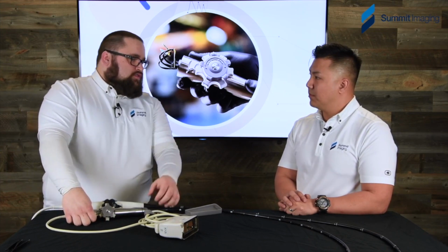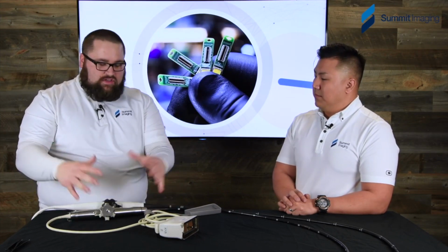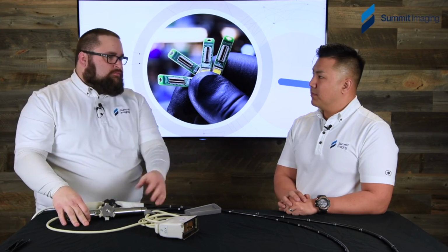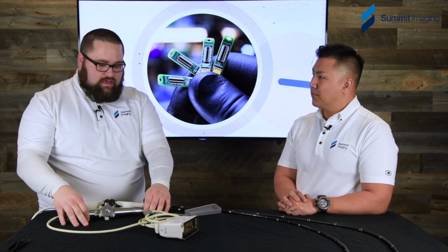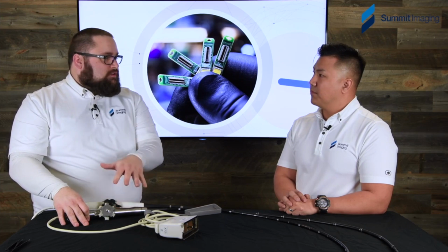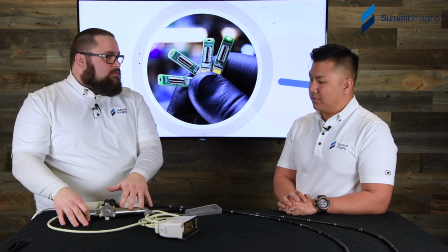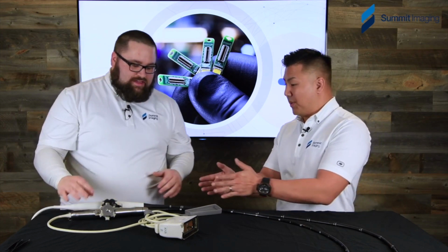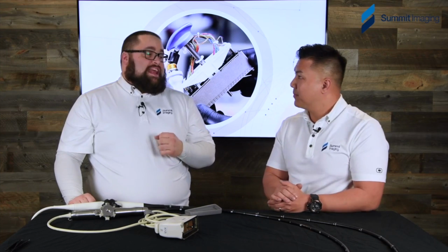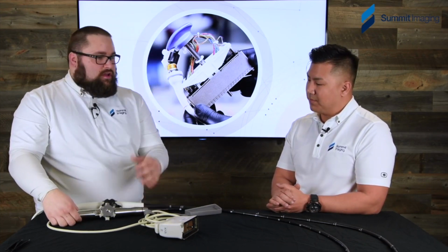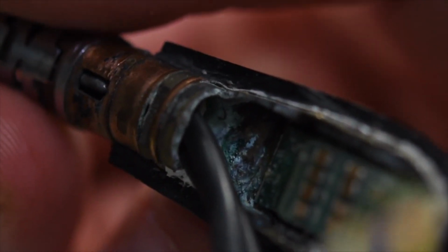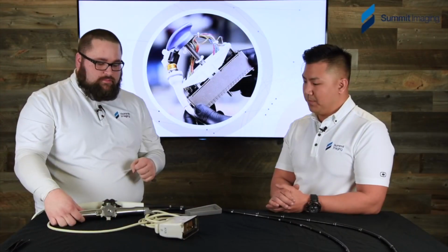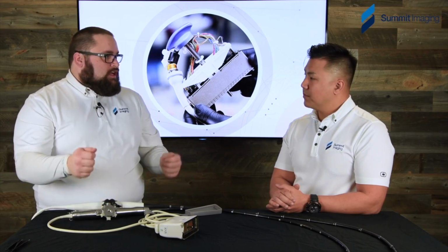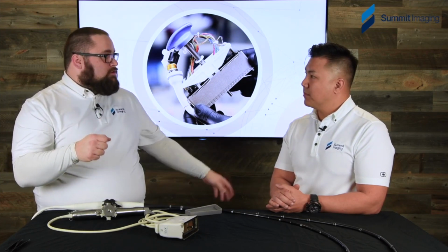Now, it goes downstairs Friday at 4:30, and it sits till Saturday morning or worst case Monday, and that sponge just had all that time to let its rather low acidic cleaning solution get in here, but it's still soapy. It's gooey. We've had lots of probes opened up where the point is it's fluid and it's still getting in. It's getting in there, and it's nasty stuff too. So it's actually a lot trickier to clean that up because not only are you looking at corrosion, but you're looking at usually a buildup of some kind. Whereas in the OR, all I had to do was wipe it with a sponge and into the garbage, into the medical waste, and everything would have been solved.